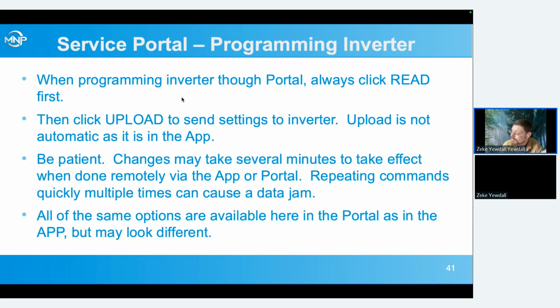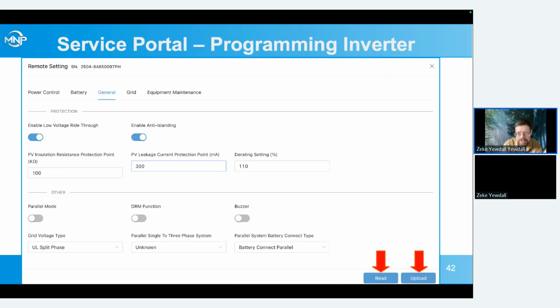When we're programming the inverter through the app, changes occur right away. When we're programming it through the portal, here's what it looks like. You'll have in the lower right corner a read and an upload button. When you first open this box, you want to hit read so you can see what's actually there now. Sometimes it'll have old data from last time you were working with this inverter. So you always want to hit read first, and then once you've made the change you want, hit upload to send them to the inverter. It's not automatic when you make the change.